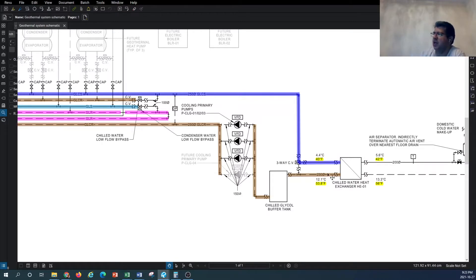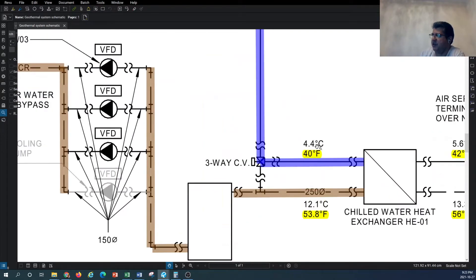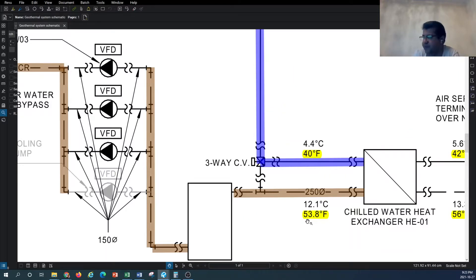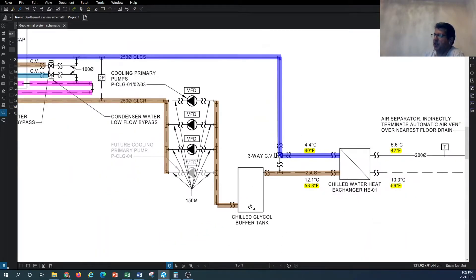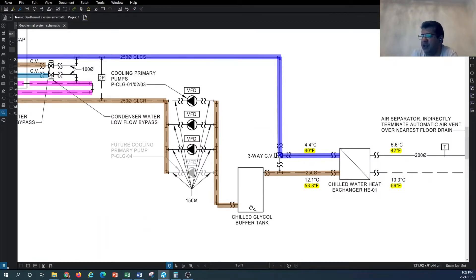On the supply side we have 40°F, and on the return side we expect to see approximately 53.8°F. Sometimes the return temperature is not as expected, which is why we have a chilled glycol buffer tank — to ensure the chilled glycol return remains within the required temperature range.